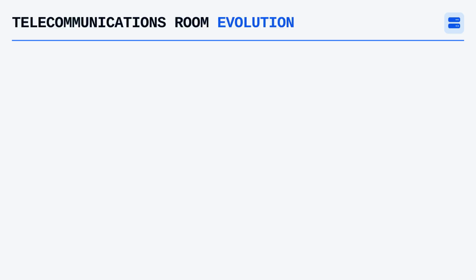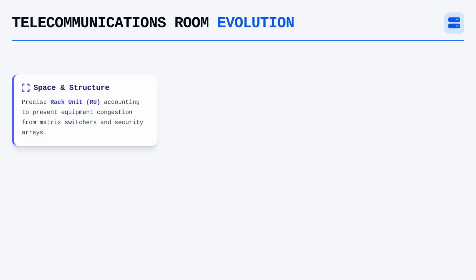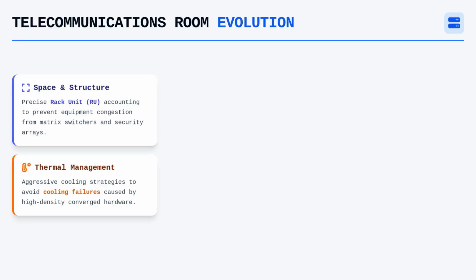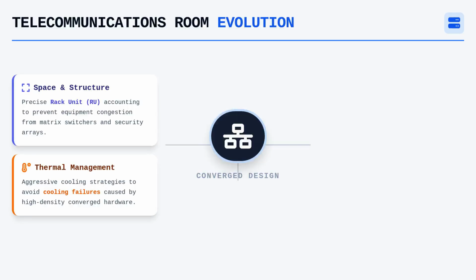The telecommunications room itself must evolve to manage the added stresses of these converged systems, specifically regarding space allocation and thermal management. A standard TR design that ignores the footprint of matrix switchers and massive intrusion detection arrays will eventually suffer from equipment congestion and cooling failures. Each rack unit of space must be accounted for during the planning phase, ensuring that the cabinets themselves can support the structural weight of specialized AV hardware.